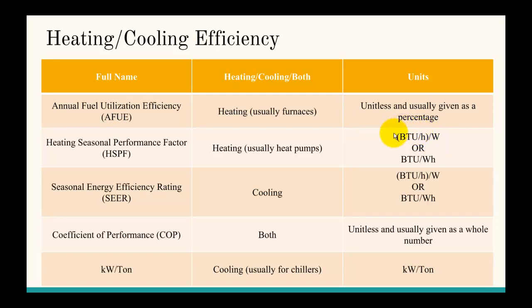They're in either BTUs per hour per watt or BTUs per watt hour. The general reason is because the output of a heat pump is usually measured in BTUs per hour or BTUs, and the input is electricity, which is usually measured in watts or watt hours.